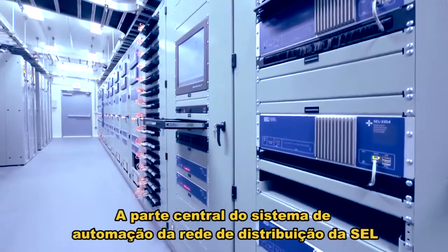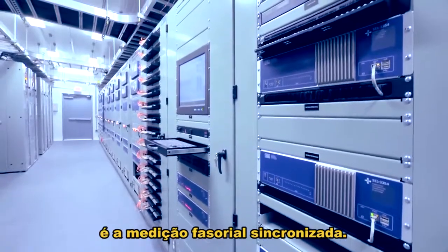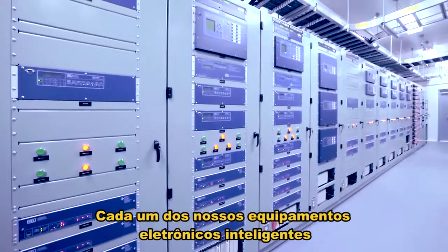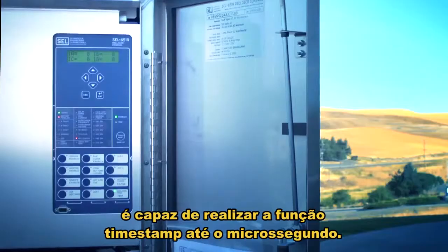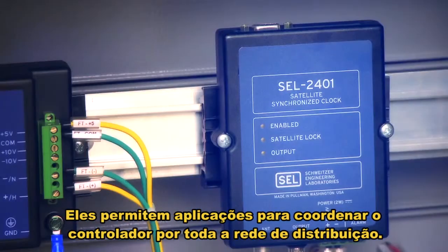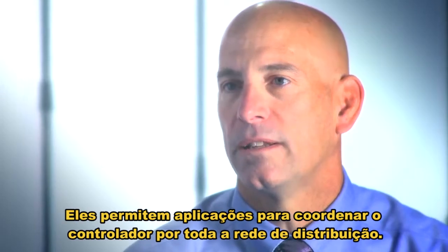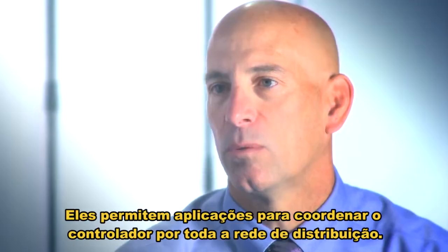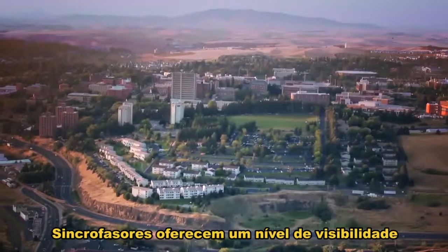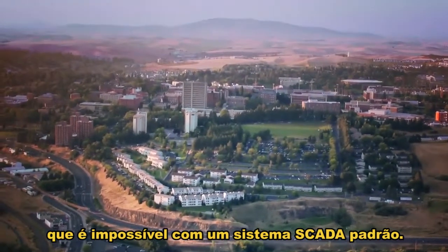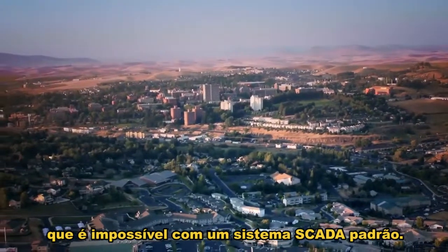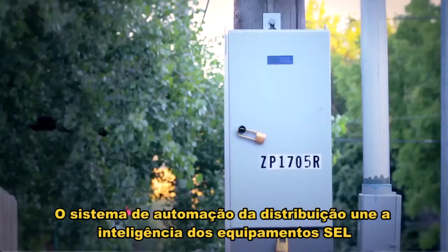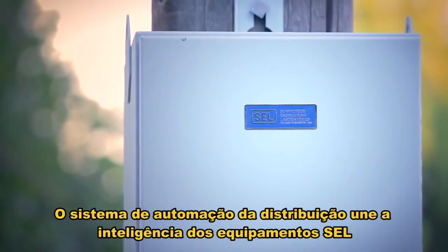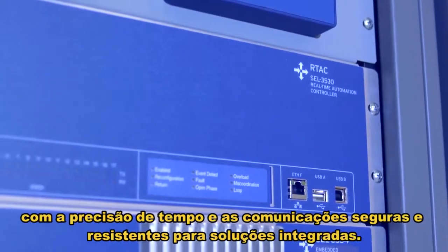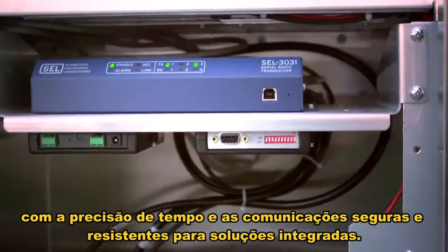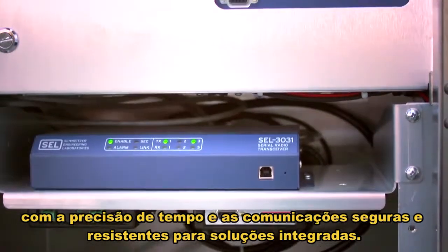The central part of the SEL DNA system is synchronized phasor measurement. Each one of our intelligent electronic devices is able to timestamp down to the microsecond. It enables applications for coordinating the control across your distribution network. Synchrophasors offer a level of visibility that just isn't possible with a standard SCADA system. The DNA system is really cool in that it ties together the intelligence of the SEL devices with the precise timekeeping and the rugged, secure communications for an integrated solution.